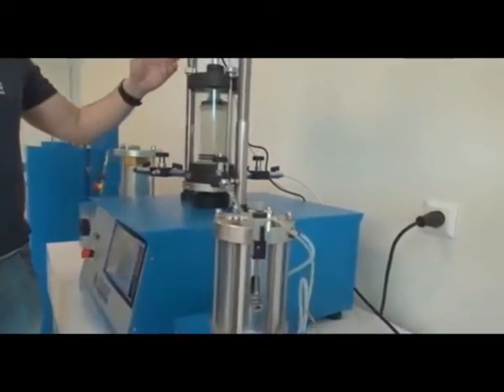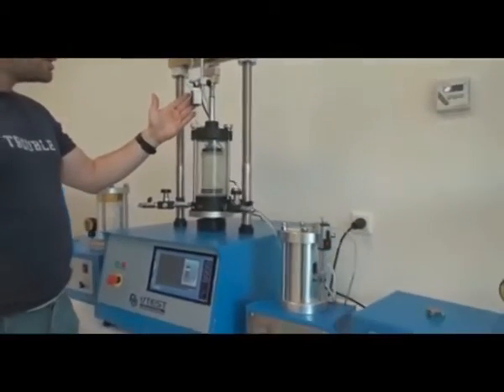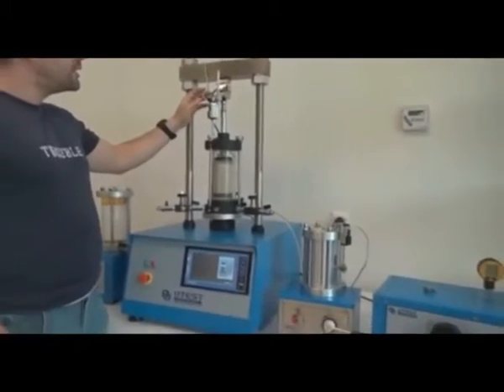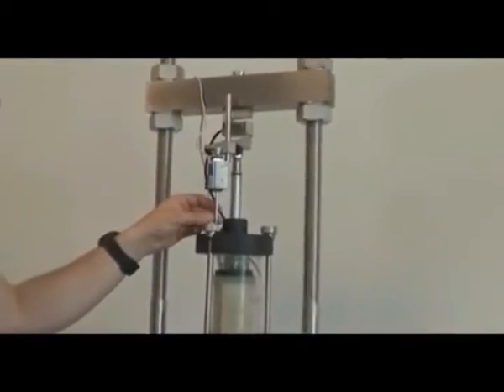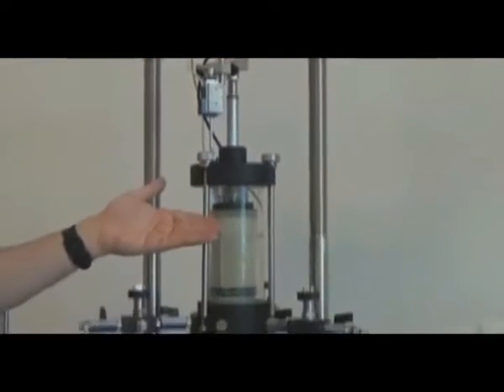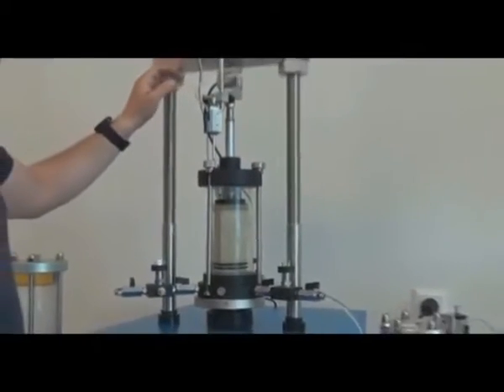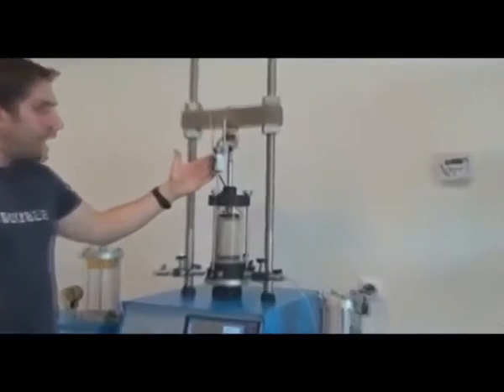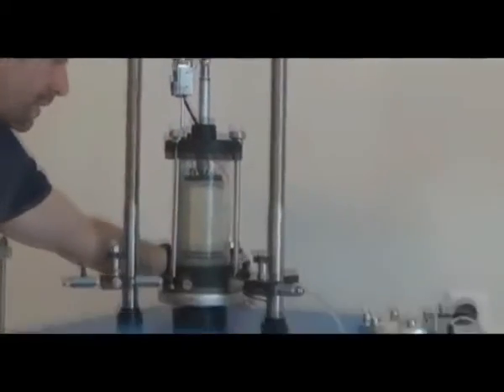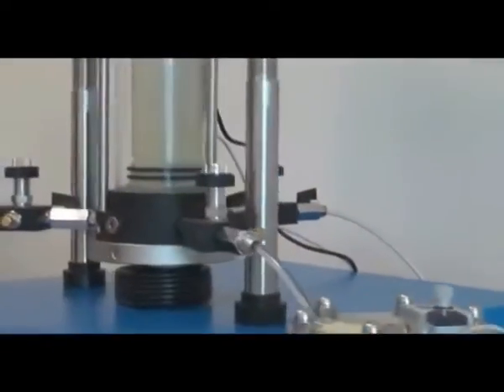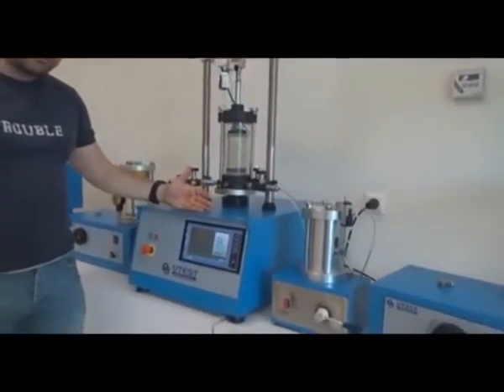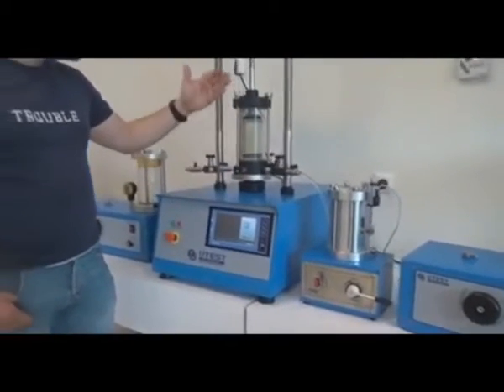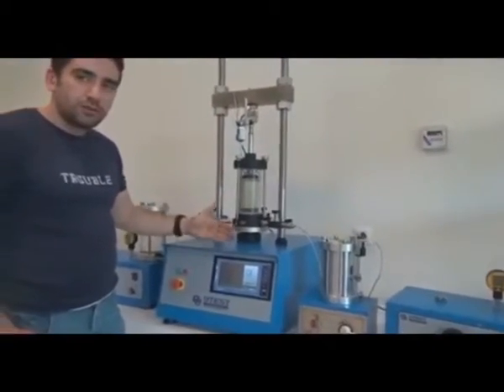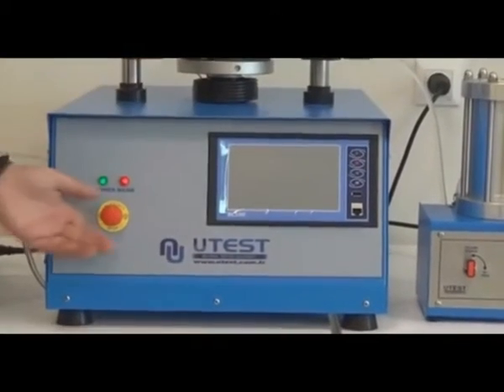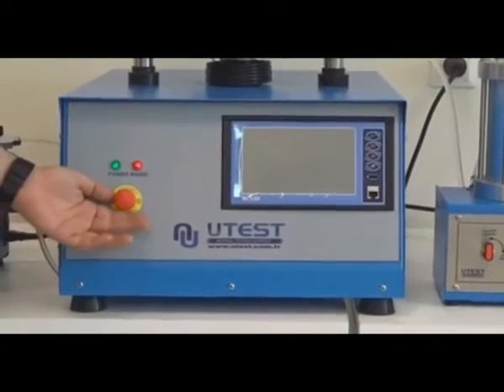And we also have a linear variable displacement transducer, which is called the LVDT for short, mounted on the device, which makes it possible to measure the vertical displacement of the specimen. This load cell and the LVDT are directly connected to the multiplex machine from the backside. The load cell and LVDT communicate with the machine, and while conducting the test, they determine the speed and the load values to the machine. Here on the multiplex machine, we have an emergency start and stop button.